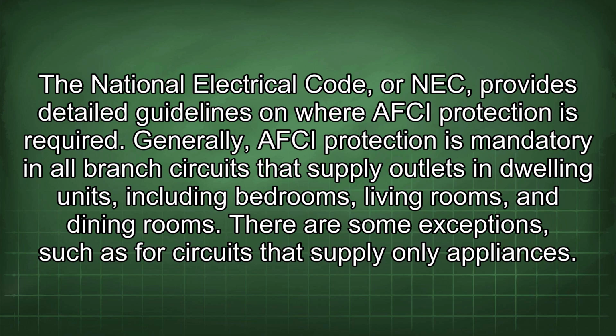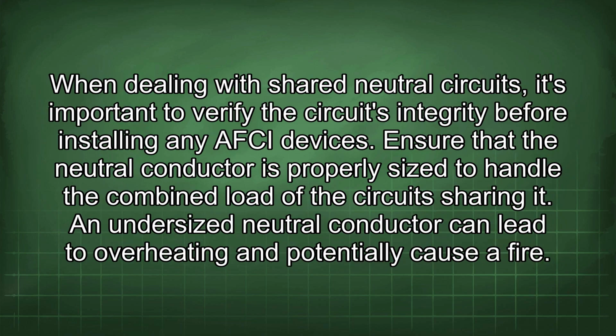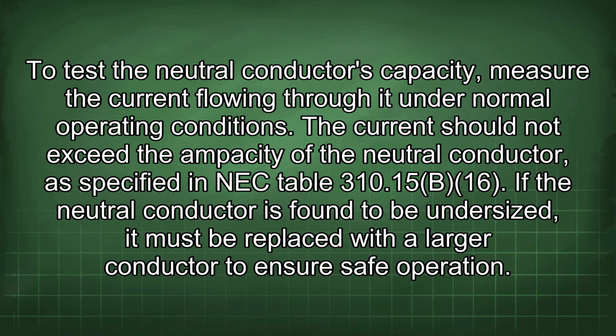Generally, AFCI protection is mandatory in all branch circuits that supply outlets in dwelling units, including bedrooms, living rooms, and dining rooms. There are some exceptions, such as for circuits that supply only appliances. When dealing with shared neutral circuits, it's important to verify the circuit's integrity before installing any AFCI devices. Ensure that the neutral conductor is properly sized to handle the combined load of the circuit sharing it. An undersized neutral conductor can lead to overheating and potentially cause a fire. To test the neutral conductor's capacity, measure the current flowing through it under normal operating conditions.